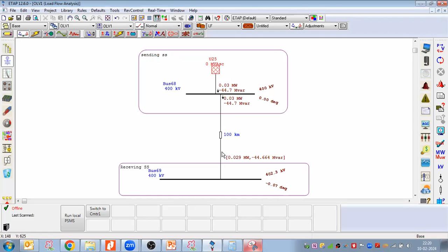Here I don't have any source; I have the source here. From here to here is a transmission line, and from the receiving substation towards the sending substation I'm sending the power. Could you see that now the grid is operating at minus 44.664? That means I'm not taking power from the grid, I'm injecting power into the grid. At this point, minus 44.664 MVAR is the power generated by the shunt capacitance.